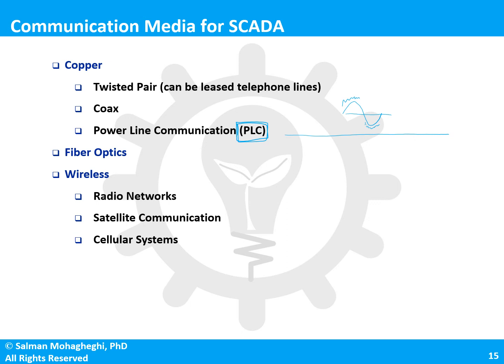Another option is fiber optics. Fiber optics are very efficient, but expensive compared to copper. However, they offer resilience against cyber intrusion, because a hacker is not going to be able to tap into a fiber line as easily as they could with a copper line. So whenever cyber intrusion is a concern, fiber would be a very good option. Of course, fiber offers much higher data rates than copper. It's immune to electromagnetic interference, so there are a lot of positives with that.